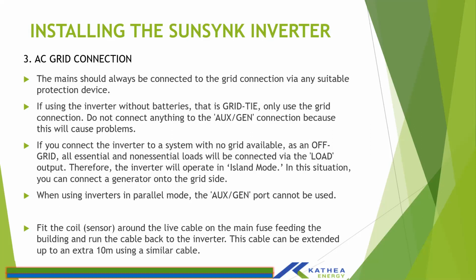When you are wiring the generator in an off-grid situation, you would wire the generator as grid input, not on the aux port. Whether you have a single inverter or parallel inverters, the generator will be wired on the grid input. So if you're in parallel mode in an off-grid scenario, you wire your generator on grid, so you are not using the aux port. But in a scenario where you have a grid connected on the grid point, and you want parallel inverters, then you cannot use the aux port, because the grid port is already occupied.